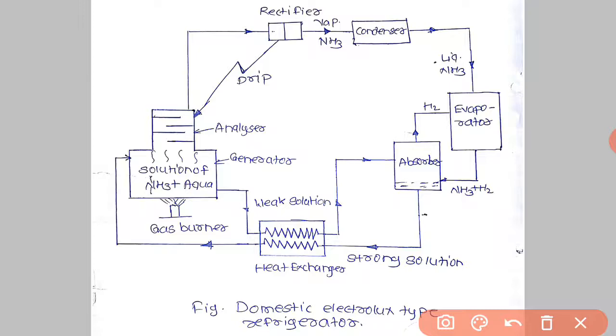Hydrogen is the lightest gas, so it is used to increase the rate of evaporation in the system. The hydrogen is non-corrosive and insoluble in water, so this is used in the low pressure side of the system. The water is used as a solvent. See here, water is used as a solvent because it has the ability to absorb ammonia readily.